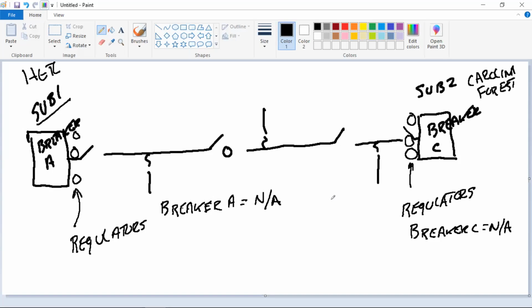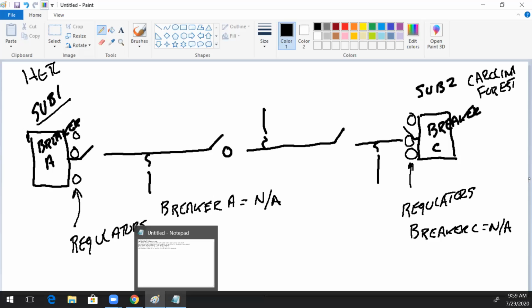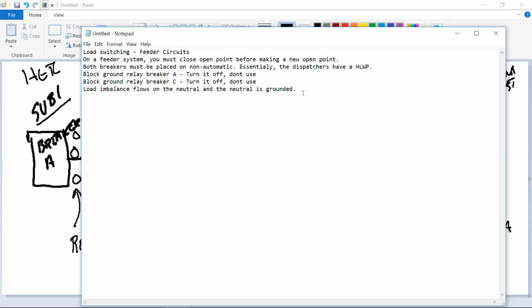Now, luckily out there, the information that the dispatchers are getting back from the regulators is not at the primary voltage, it's at the secondary voltage. And usually it's right around 120. That's what we want on our system. So what we'll have to do in the procedure to be able to close this switch to start is match regulators on breaker A, and it doesn't have to be exactly 120. It could be anywhere in the full range that we have, 126 to 114, as long as it matches the other station.